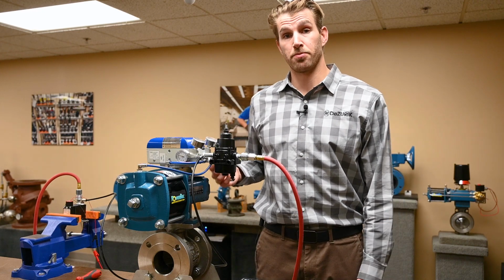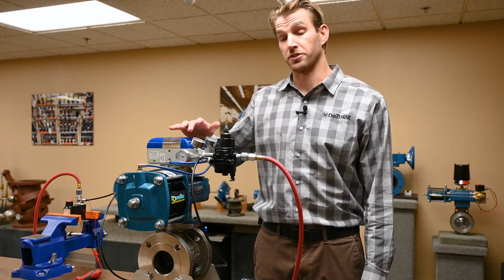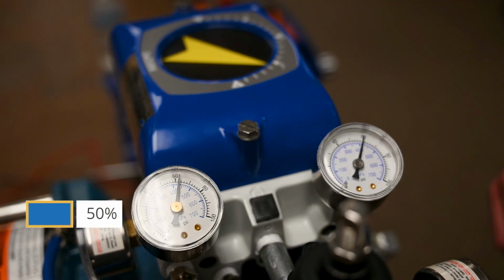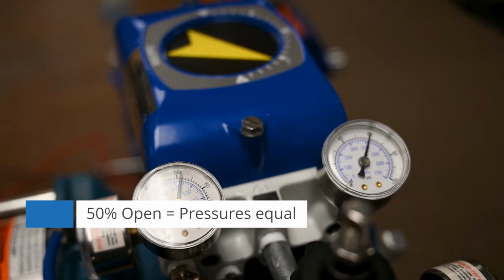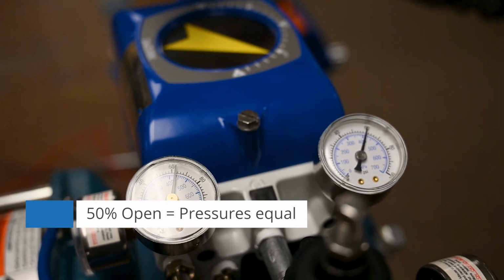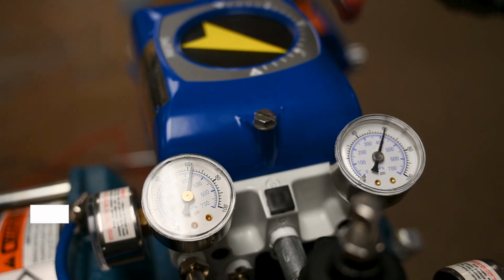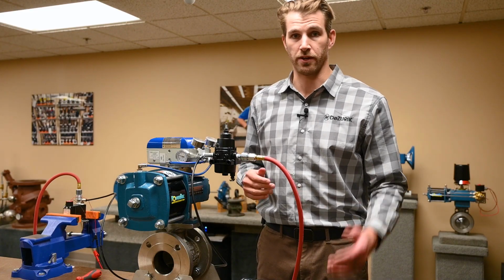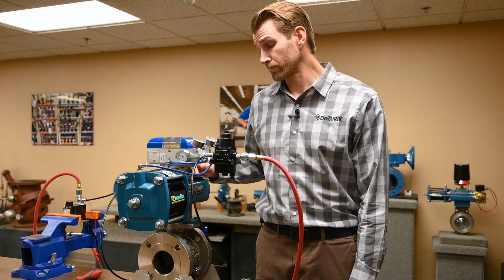The gauges on the top of the positioner, located here, are measuring the pressure that's being sent to the open port and the closed port of the actuator. In this case, being 50% open, the pressures are approximately equal, which makes sense, the valve being at midway open.